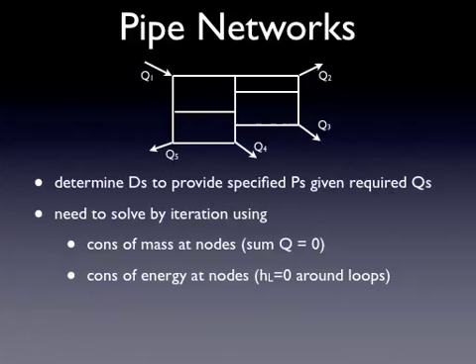And so then you go through and you write a head loss equation for each loop. So you get this big long list of equations. If you solve them all simultaneously, it will give you the flow rate in each pipe. So you can pick a bunch of diameters, see what the flow rates are, see what the pressures are. And if that works, you're done. If not, then you change a couple diameters, resolve it.